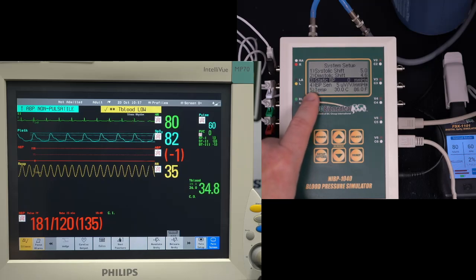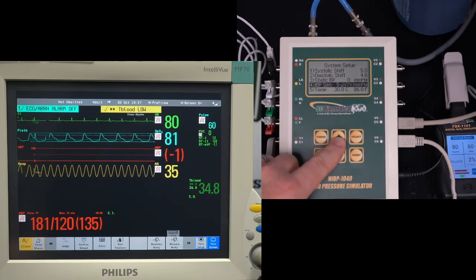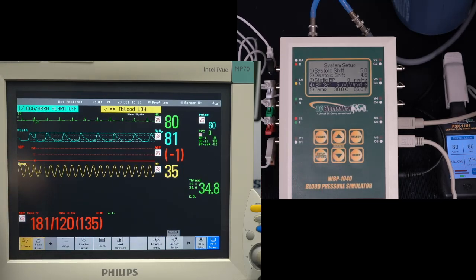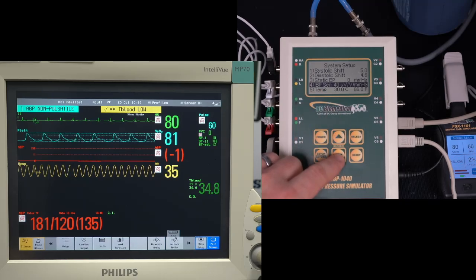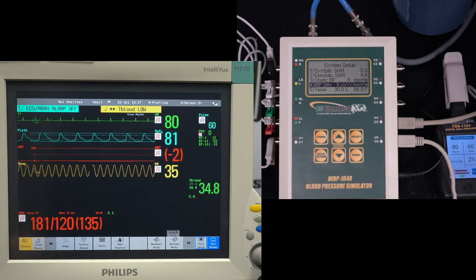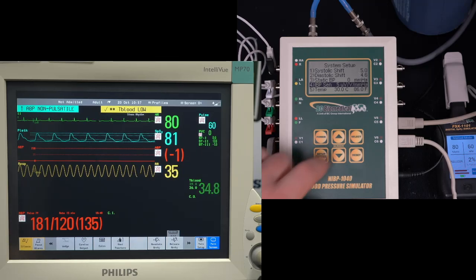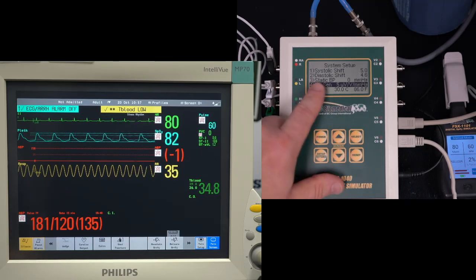I also need to make sure that the sensitivity is set correctly, because just like the respiration, the monitor is configured for a specific sensitivity of voltage to millimeters of mercury. The options are 5 and 40. Obviously, if you don't have the right value set, then the monitor is going to get the wrong signal and it's going to measure the wrong invasive blood pressure. The other thing is there are different cables, so sometimes the cable changes, whether it's 5 or 40. So there are a lot of things to be aware of and careful about to make sure we have the right configuration.